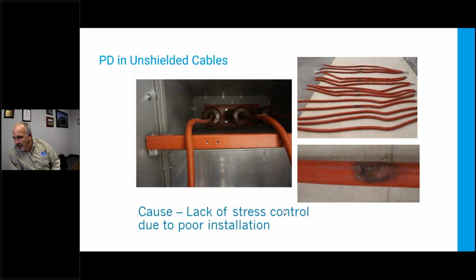Here's a tricky one. This is one of my favorites. This is an installation where they had the unshielded jumper cable, and those of you who have worked with unshielded jumper cable know it's terrible stuff, and especially for PD. It may withstand the voltage, it may do a high pot, but it doesn't withstand the field. And so in this example, they've got a brace that comes out here, and that corner of the brace is resting on the round edge of the cable, and that small geometric point is causing a discharge. And even though you could high pot this, you could measure it, you could do whatever you want, it still caused discharge. And it did it from the minute it was energized until they took it out of service.